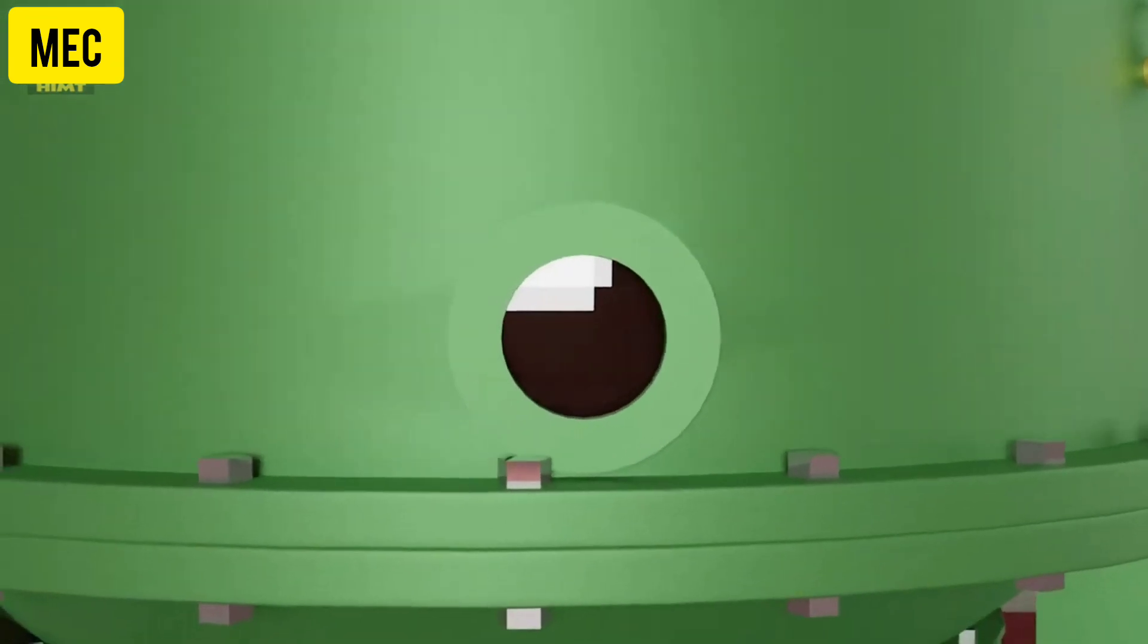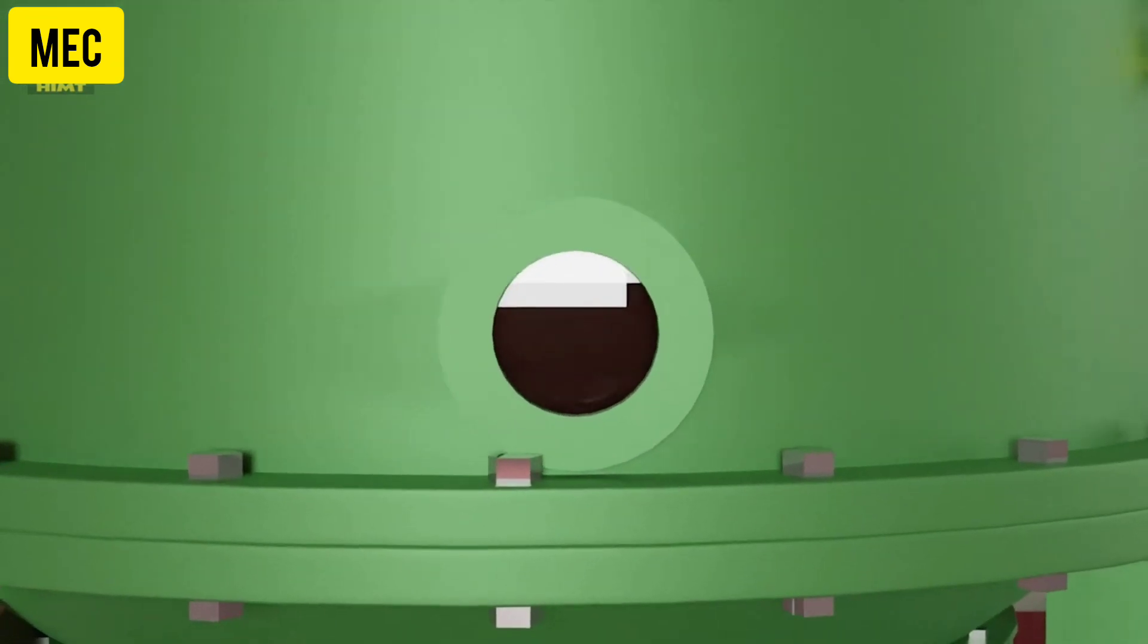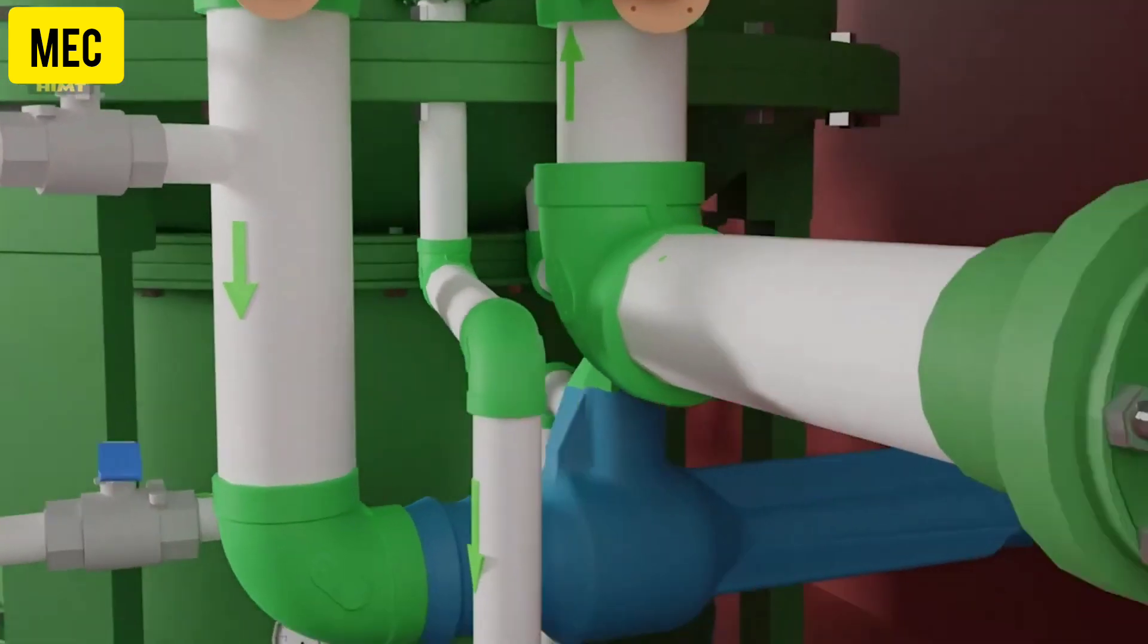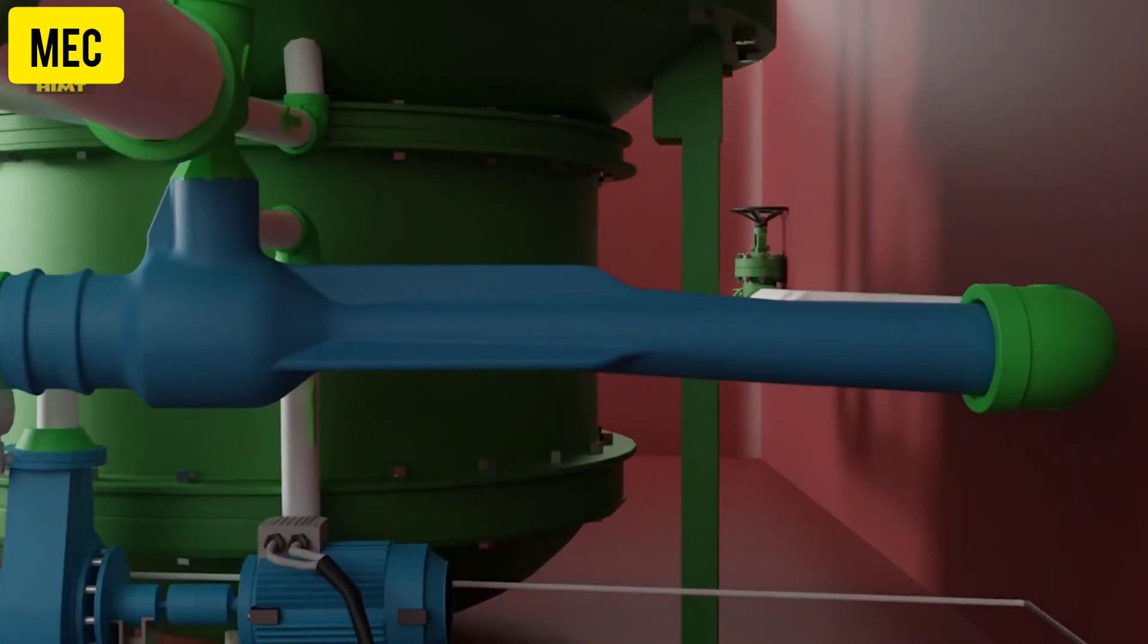This is a sight glass which shows the boiling of water inside. Next we have the eductor for maintaining vacuum inside the shell. The eductor helps to sustain the required vacuum and also aids in removing the brine. Proper vacuum is achieved through an air ejection outlet, while a separate outlet is dedicated to the removal of brine.